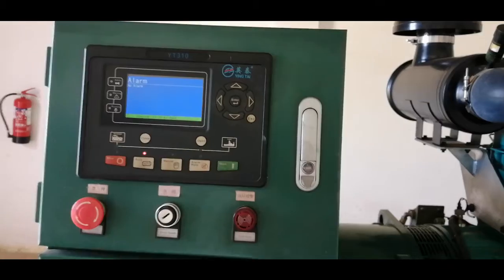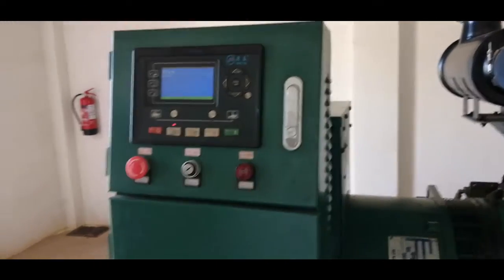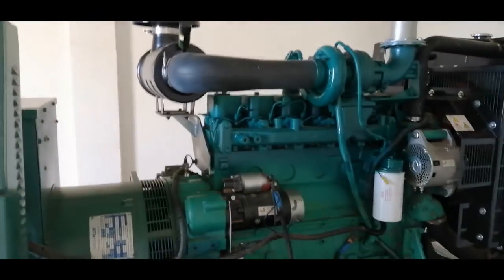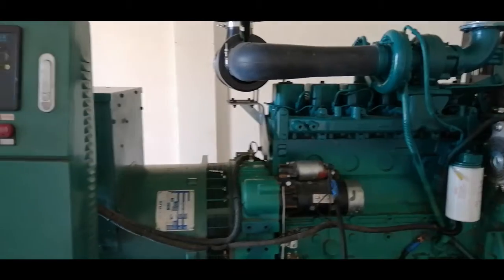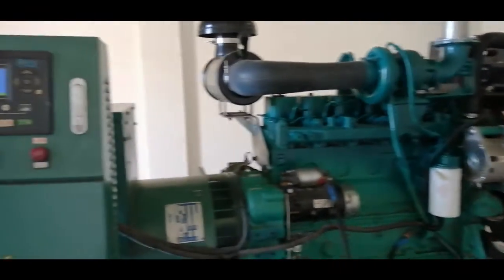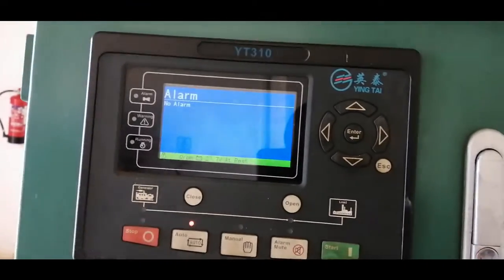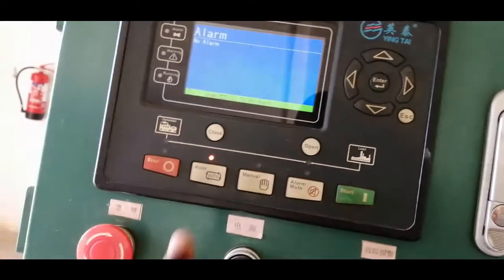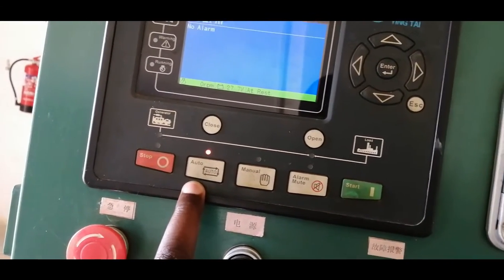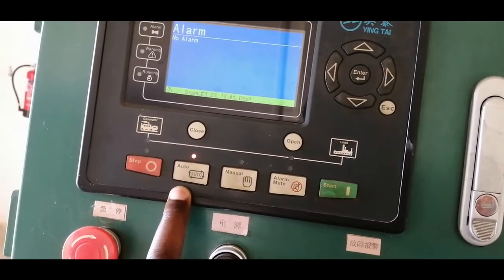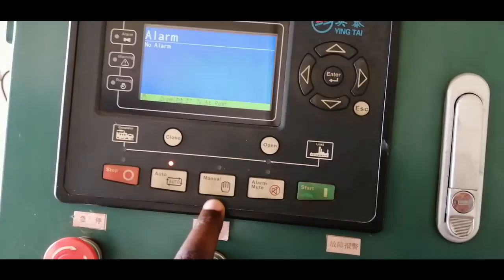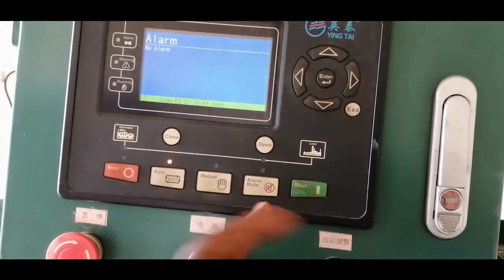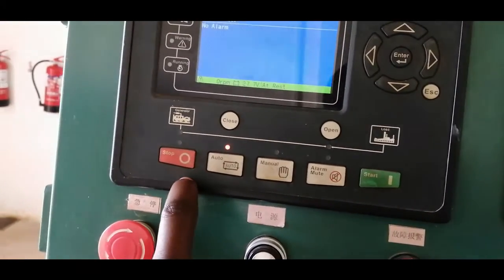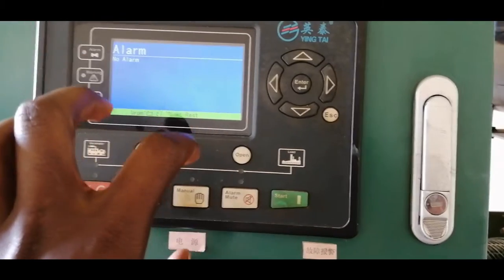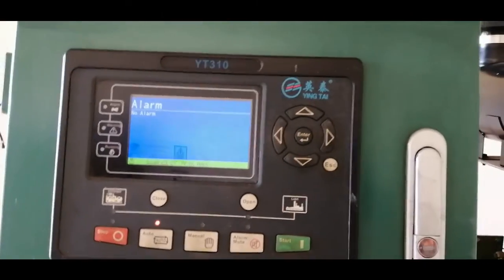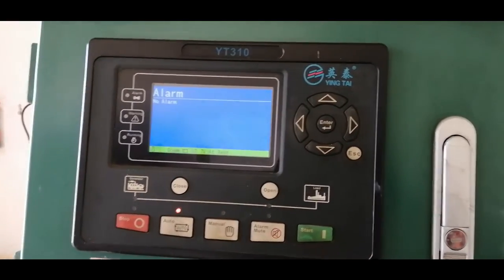Today we will be learning a few things about how we test the generator to see whether it is working well. Before any outage, we should be sure it is working very well. So when we come here to operate it, you can see right now it is in auto, meaning it can run when there is a power outage. Because we want to test it, we'll put it in manual and start it. Then when we want to shut it off, we come here and shut it off. We'll collect some data from this screen, the recording we usually make. So that's it for now, then we continue in the next.